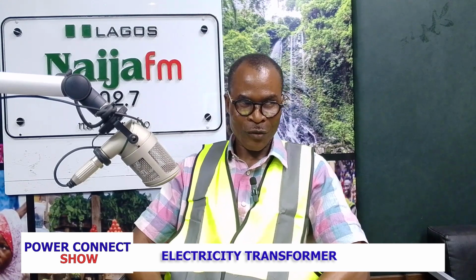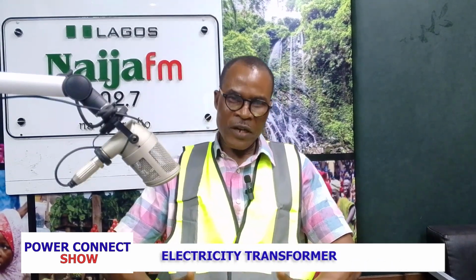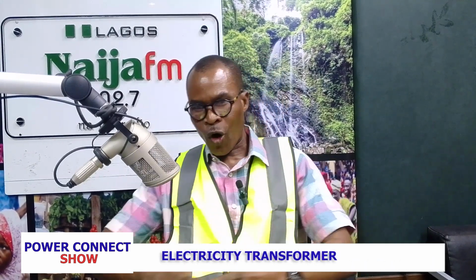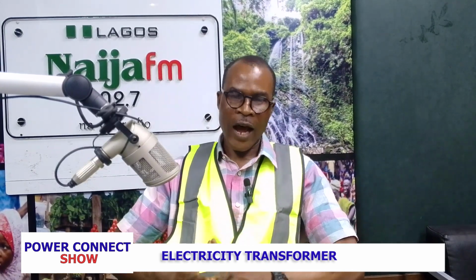The one that changes voltage from a higher level to a lower level, we call it step-down transformer. So in our setting for EKEDC, majority of the transformers we have at our distribution substations are the ones that step down. The voltage that comes in is 11,000 volts, in some areas 33,000 volts, but the one that comes out of the transformer is 415 volts. So that one is a step-down transformer.